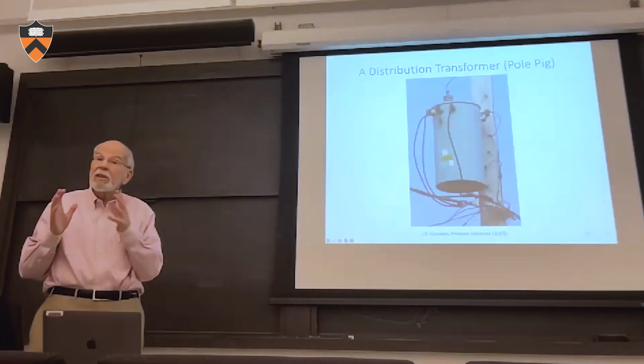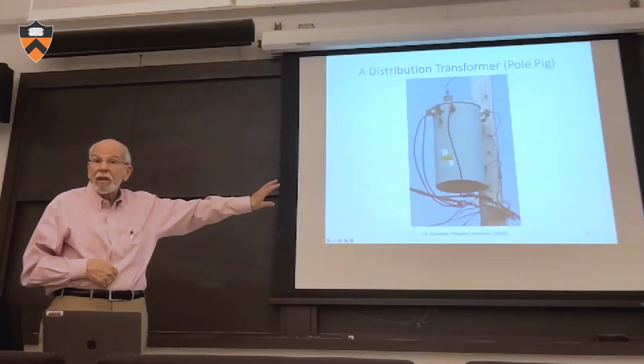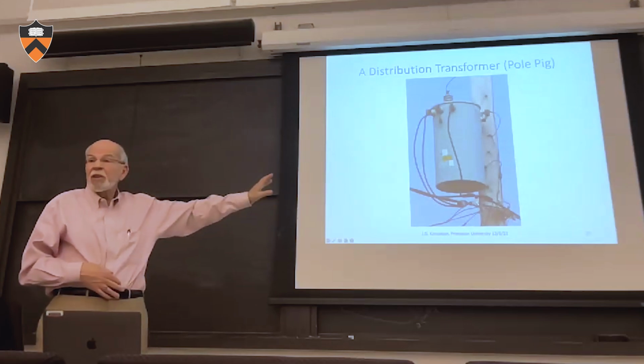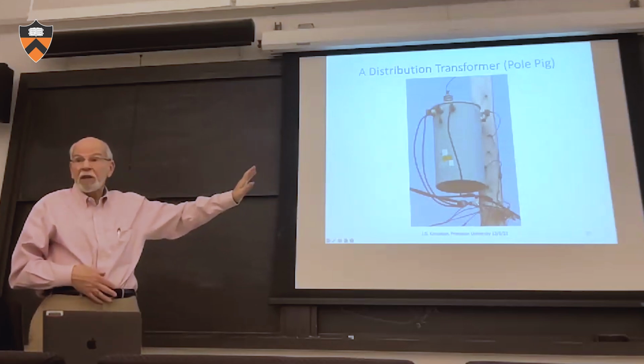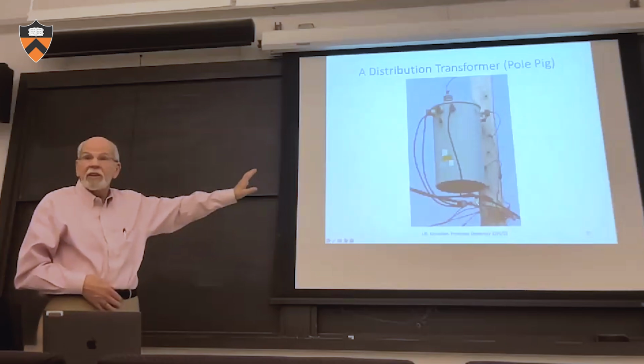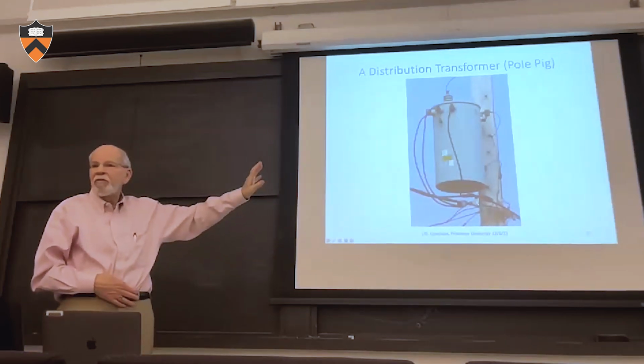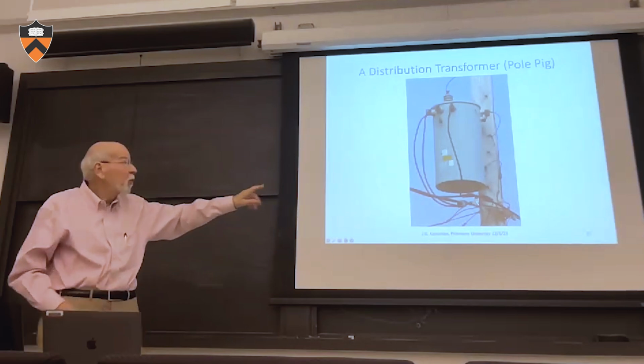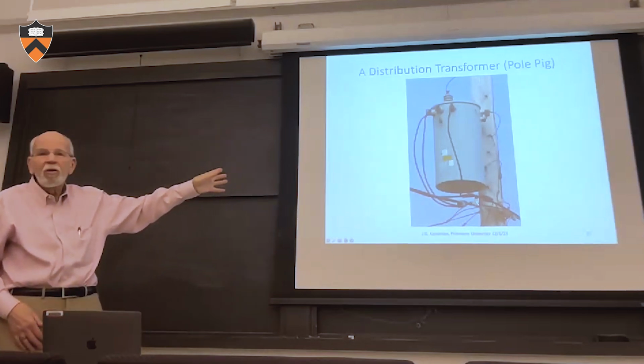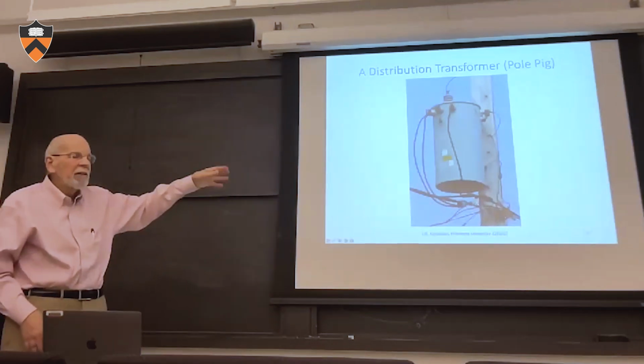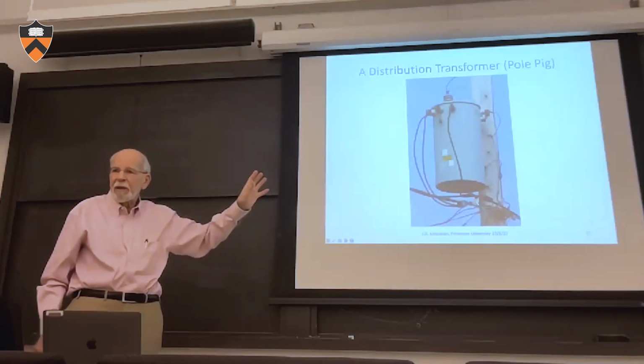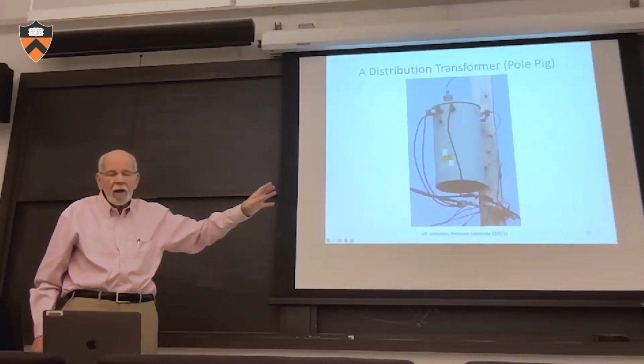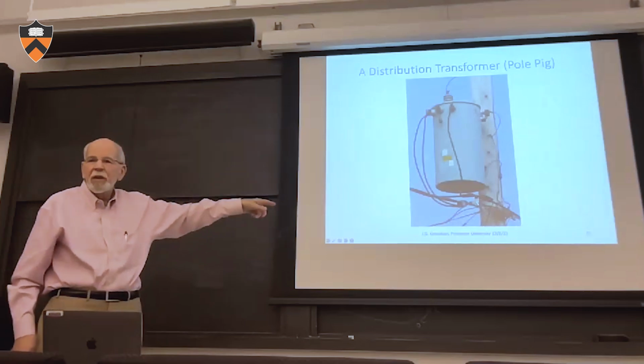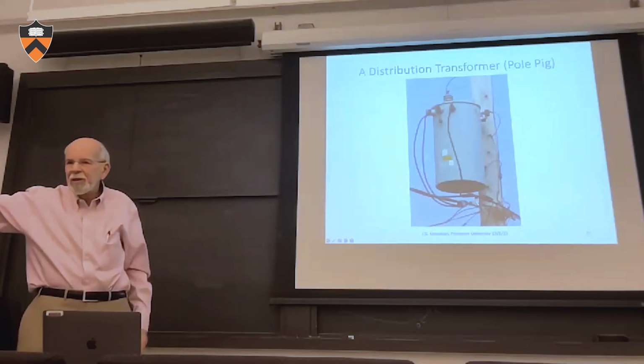It's running all the time in the sense that it's always got voltage on it. Now, if you've always got voltage on a transformer, that means you've always got core loss. So this thing is up there on the pole heating up 24/7. Furthermore, you can't control it. There's no control over that transformer. Some of them might have some tap changers or something, but basically you can't control it. And there's no communication between this thing and the utility company.